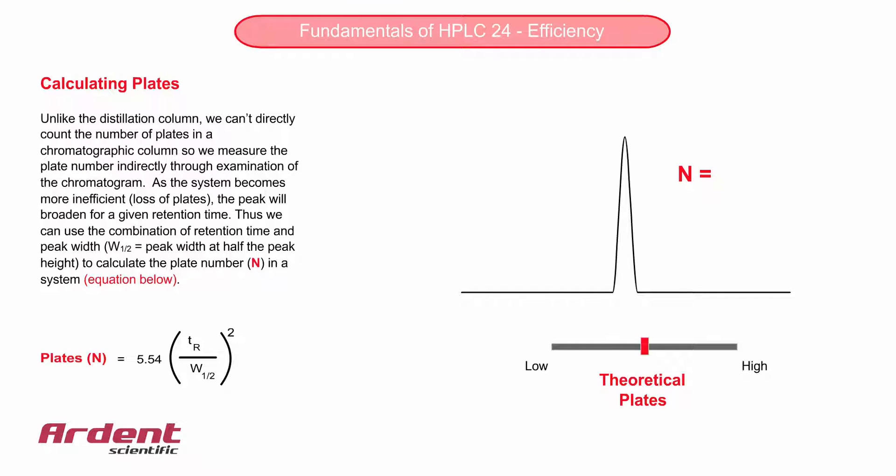Because we don't have any physical plates to count in the HPLC column, we need some other way to measure the number of theoretical plates, and thereby the efficiency of the separation.